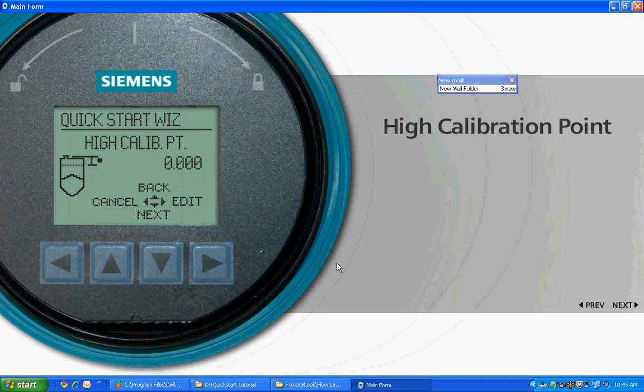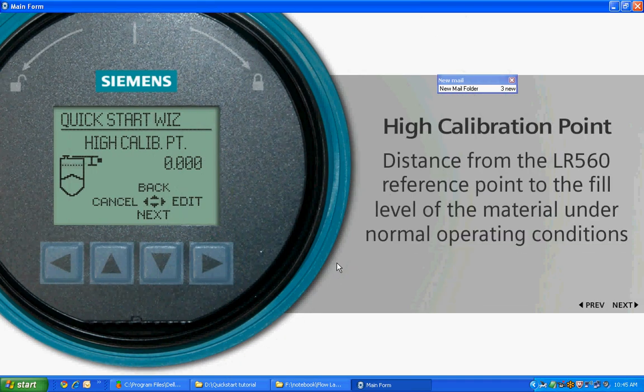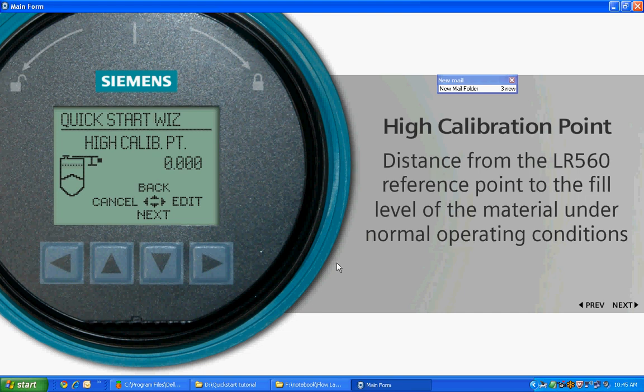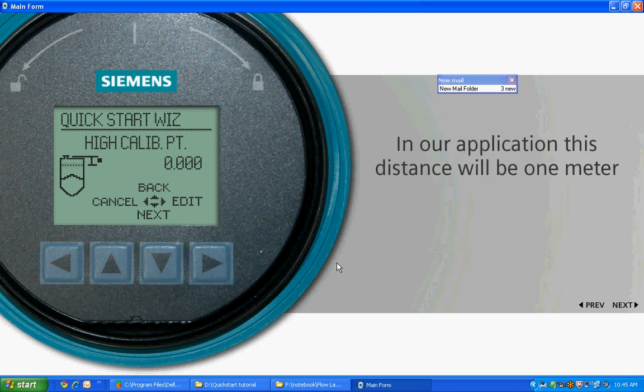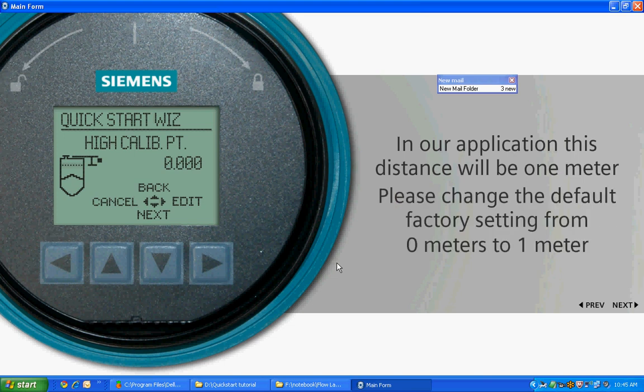The high calibration point is the distance from the LR560 reference point to the fill level of the material under normal operating conditions and represents 20 milliamps for a 4 to 20 milliamp device. In our application, this distance will be 1 meter. Please change the default factory setting from 0 meters to 1 meter.